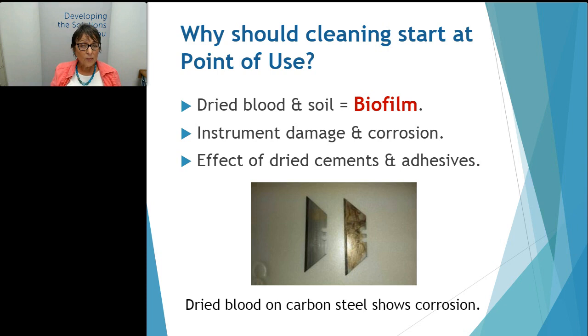So cleaning starts at point of use because dried blood and soil does create biofilm. Even on tiny surfaces, biofilm will begin to form. This is a collection of the pathogenic organisms and the soil that forms like a glue on the surface. The other problem is that dried blood creates corrosion. You can see that on the carbon steel razor blades. One blade to the left has no blood. The blade to the right, we had put some blood on it, and the corrosion happened within minutes on this carbon steel razor blade.